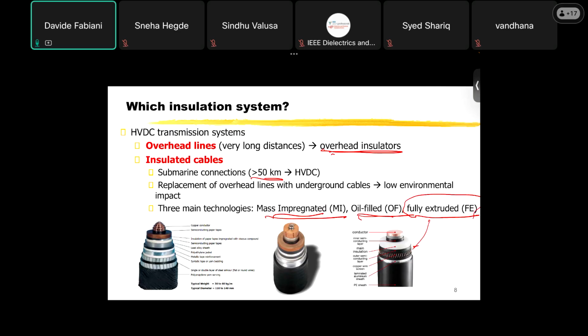And the fully extruded cables are now the frontier of the HVDC insulation systems, because they are, let's say, cheaper and also more environmentally friendly, because of course they don't use mineral oil that can be of some concern in case the cable is damaged, for instance, and it can contaminate some area, of course.